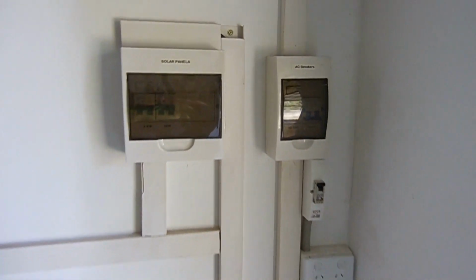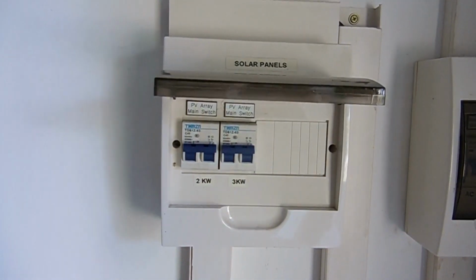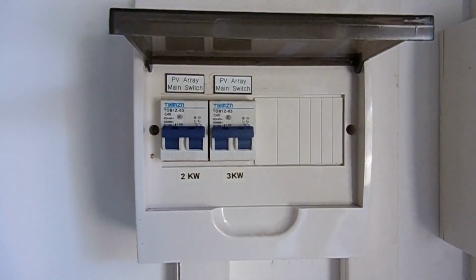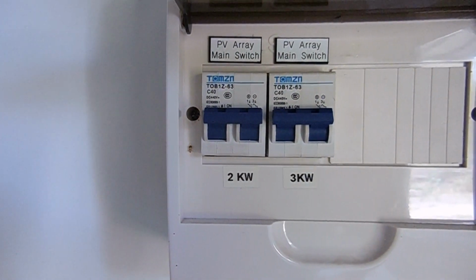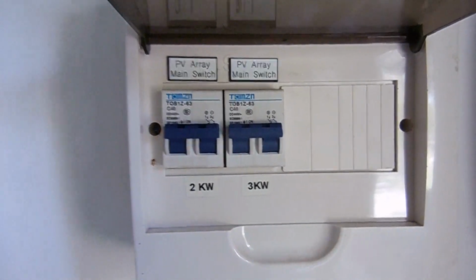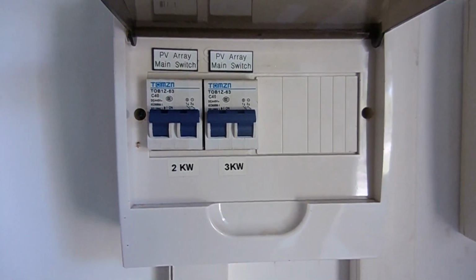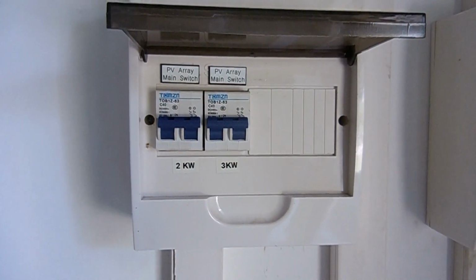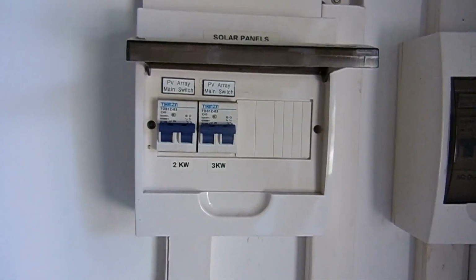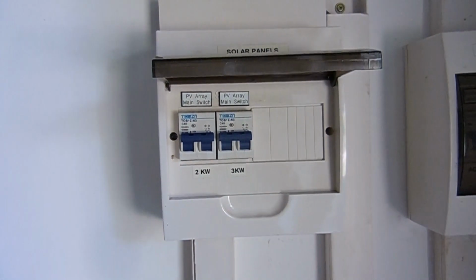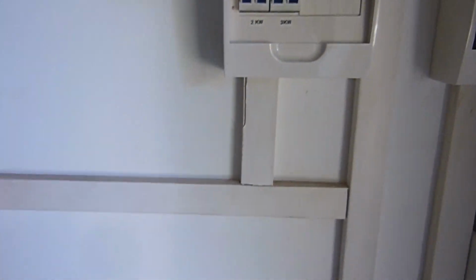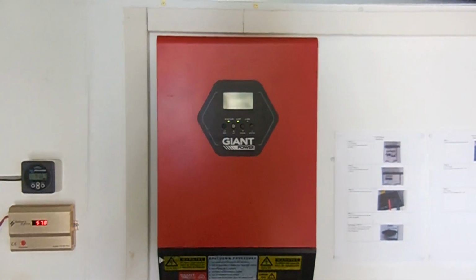Well, here we are in the power shed, and we'll start at the input where the solar panels come in. So we've got a couple of breaker boxes here on the wall. So this is where the 2 sets of solar panels come in. You can see we've got the set of 2 kilowatt panels and the 3 kilowatt panels. So there's a DC breaker on each. That's after all the panels have been combined. So from the breaker box we've got the set of 2 kilowatts and the 3 kilowatts, which travel down this conduit and go to this all-in-one inverter.